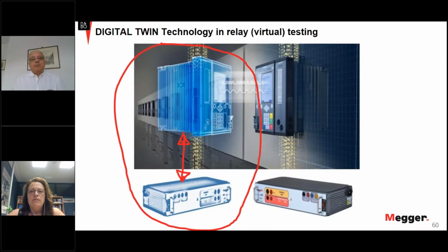And this is now digital twin. I cannot talk very much about that. There will be a new article soon on our electrical tester, but we are ready and we are developing. It's never ready, this technology, but we have developed a digital twin test set that is able to talk with a digital twin relay. Digital twin is a software copy of what the relay does in reality. So our digital twin test set is a software copy of what this guy would do. And when you save the files in the digital twin world, you can reuse them in the real world.